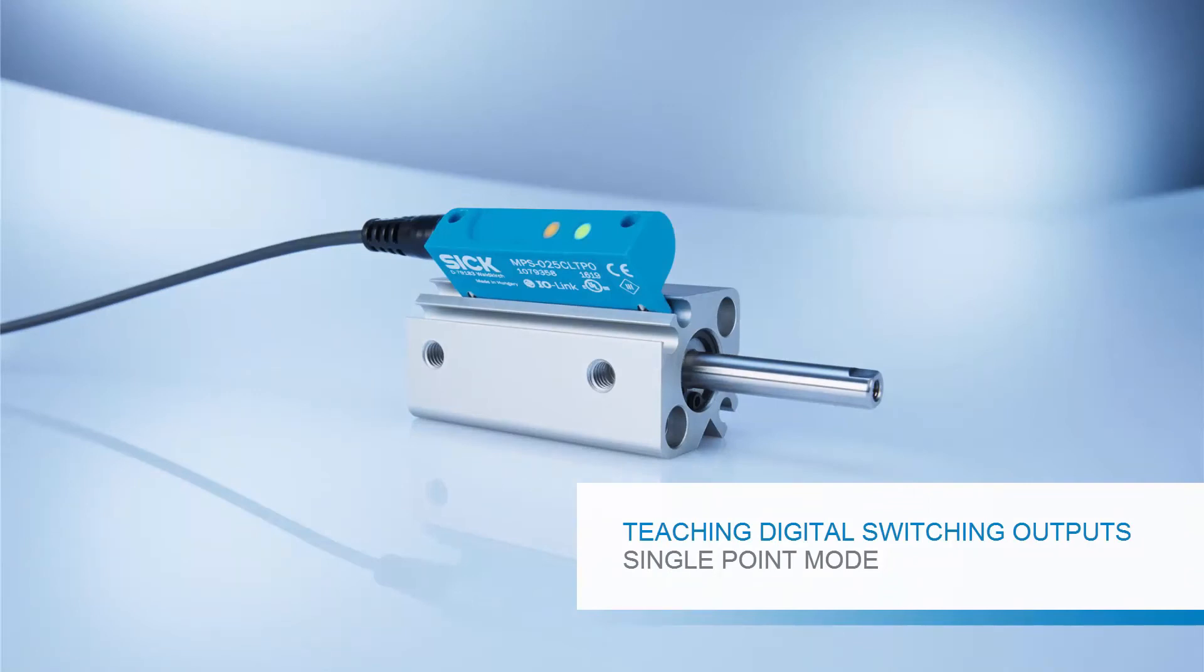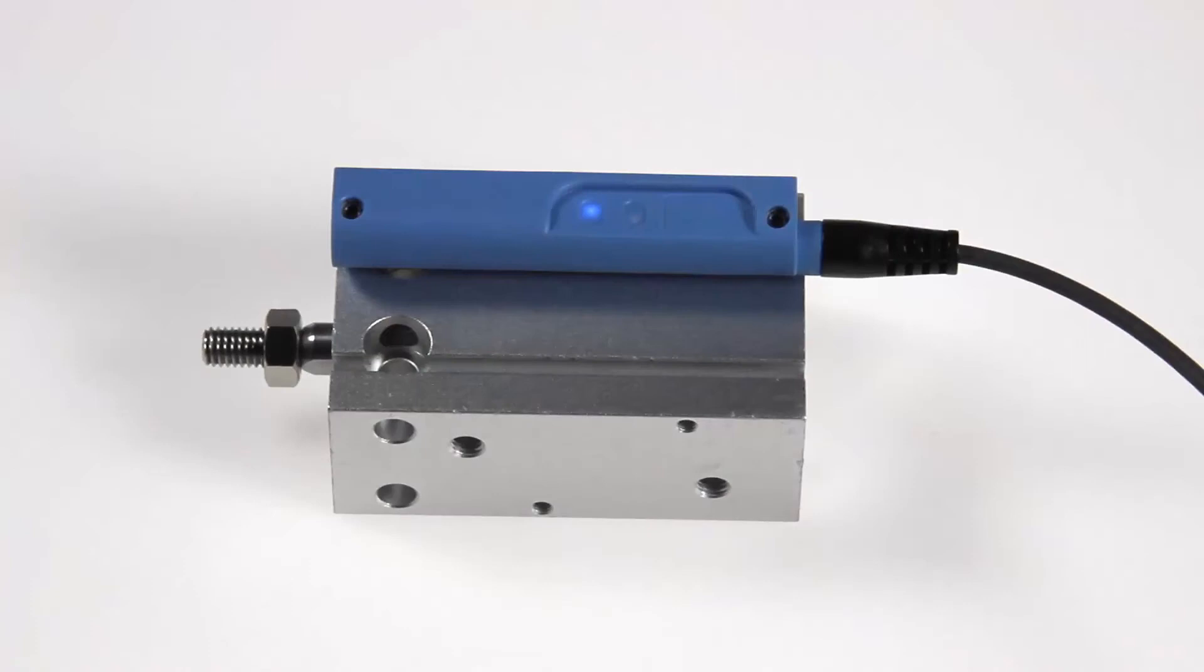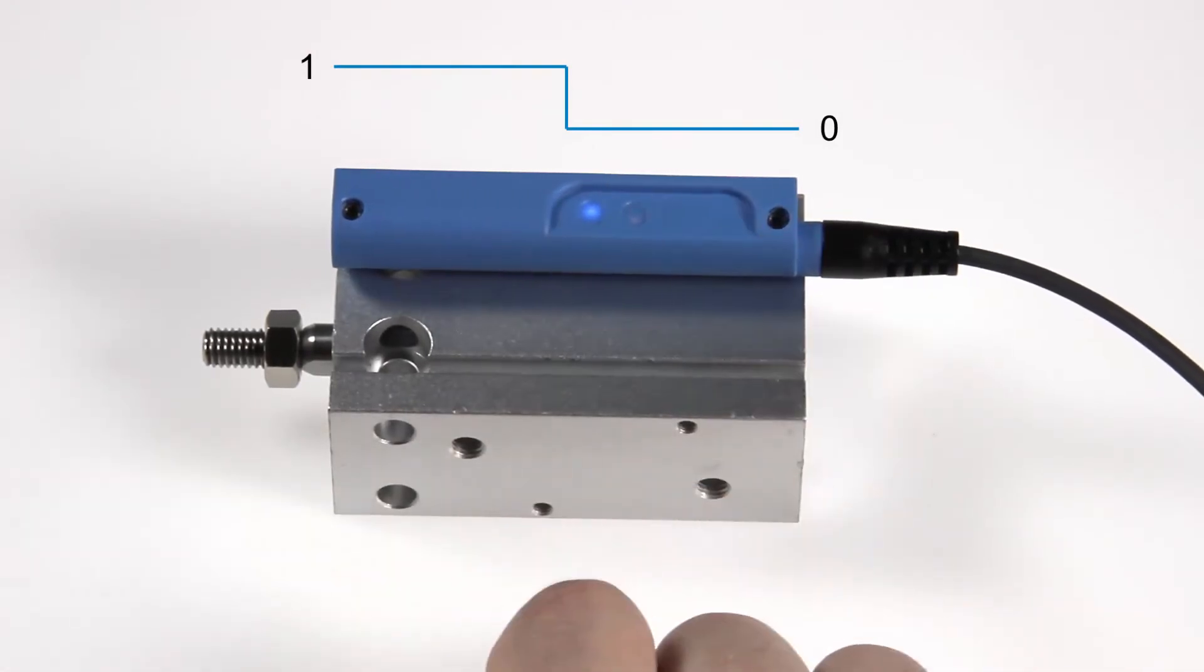Teaching digital switching outputs. Single point mode. The MPSC offers three different switching output behaviors that can be set via the keypad. The first option is the single point mode. The single point mode defines a switching point. From this point to the cable end of the sensor, the switching output is low and to the opposite direction, the switching output is active.